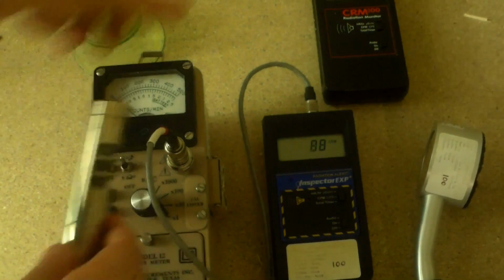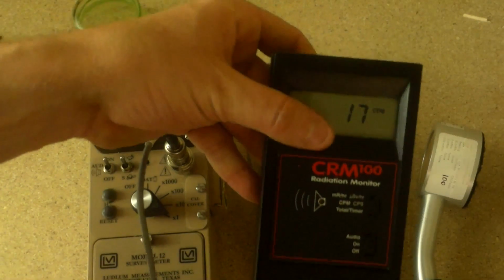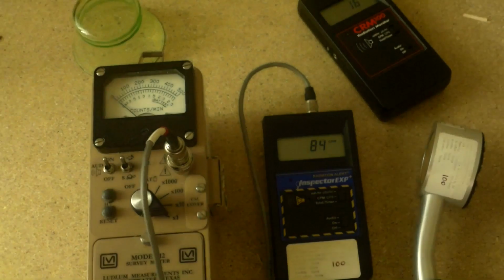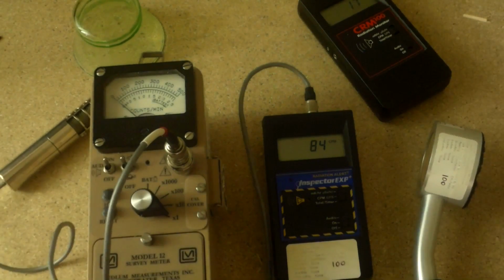The tube in here is about that long. This tube gets about 20-30 counts per minute, which is better than this tube, which is smaller. But this tube is probably better than this tube because this tube has the ability to sense alpha. Does that kind of make sense the way that's going? So it's size and the ability to detect alpha.